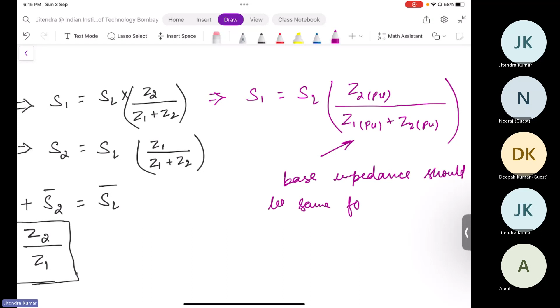So the base impedance for both transformers, both impedances, should be derived from the same base. Otherwise you will get different values. That will be much clarified in the problem. So the base impedance should be the same for both impedances.